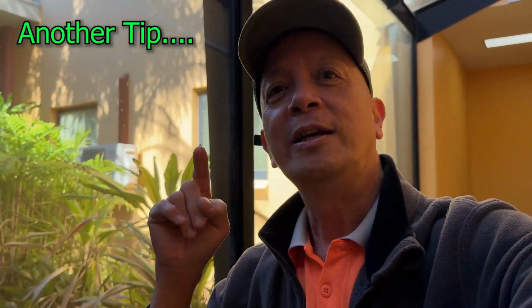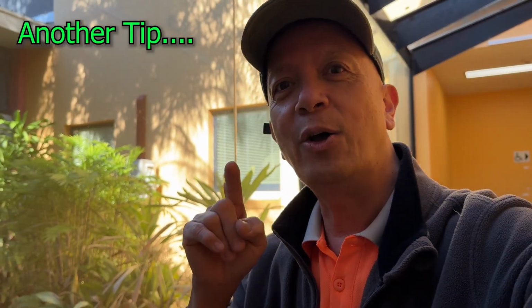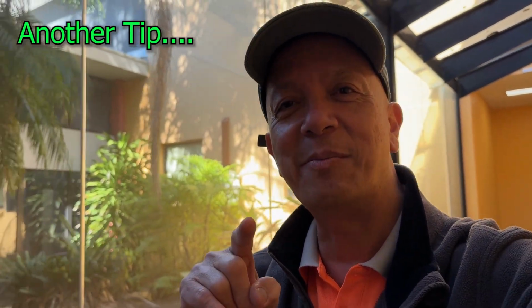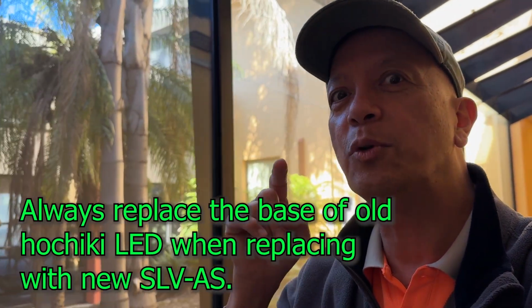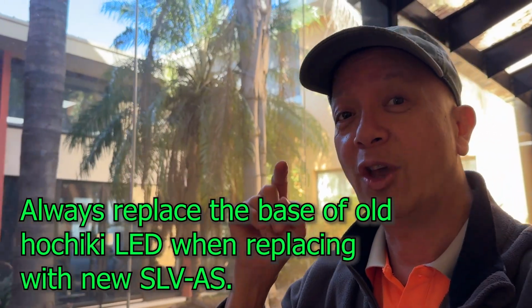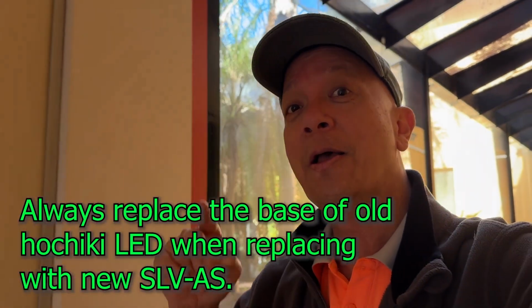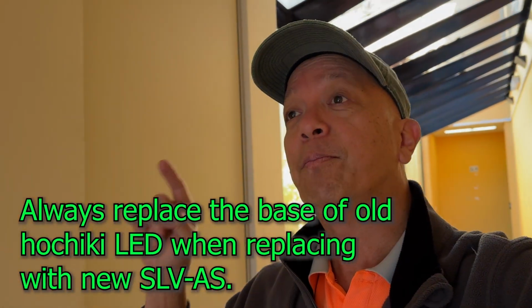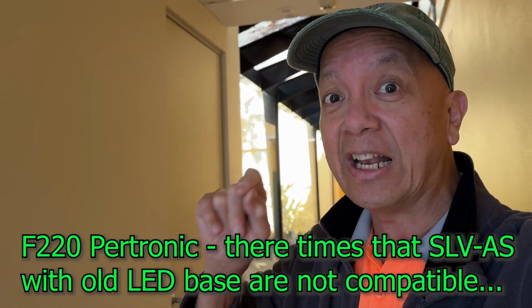One tip: if you encounter this kind of detector, it is not compatible. The new Hochiki SLV-AS is not compatible if you're using the same base, so you have to change the base as well. In a Pertronic, if you're going to reuse that SLV-AS, it will create a fault, not an alarm.